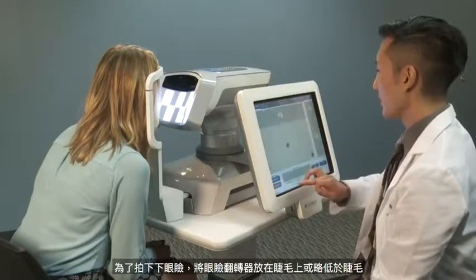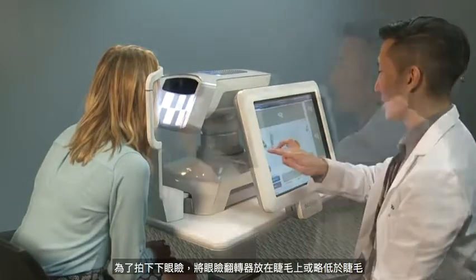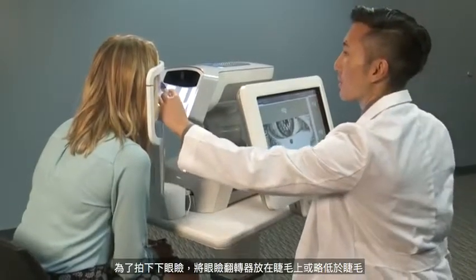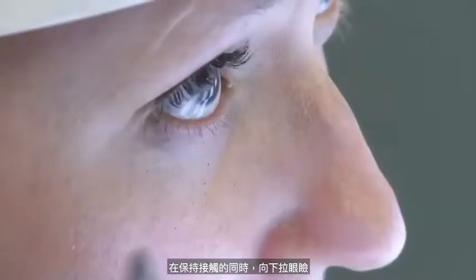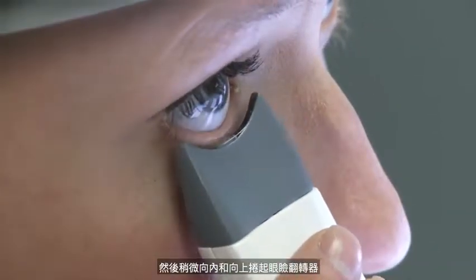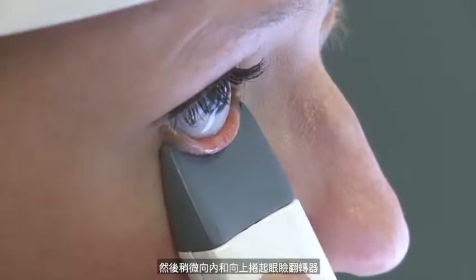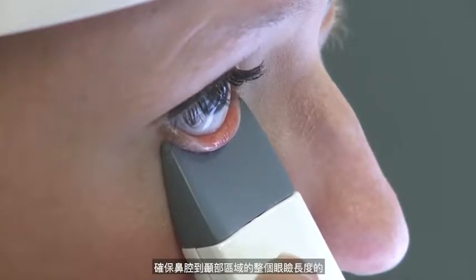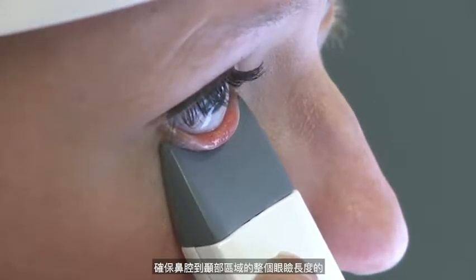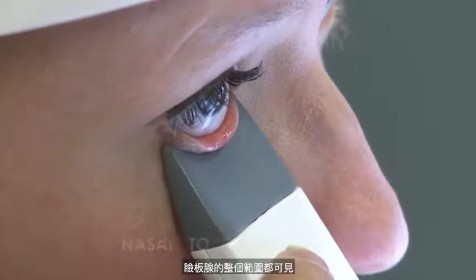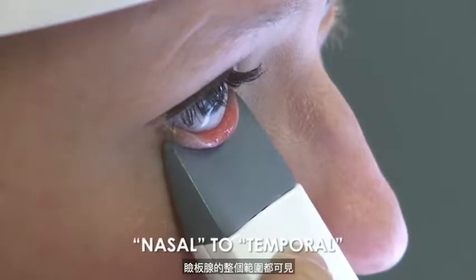To image the lower eyelid, place the lid everter on or slightly below the lashes. While maintaining contact, pull the lid down and then roll the lid everter slightly inward and upward. Ensure that the full extent of the meibomian glands is visible over the entire nasal to temporal length of the eyelid.